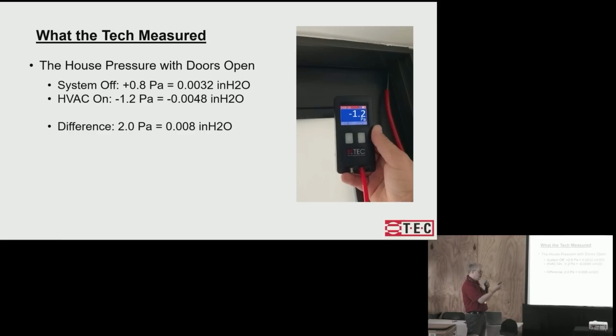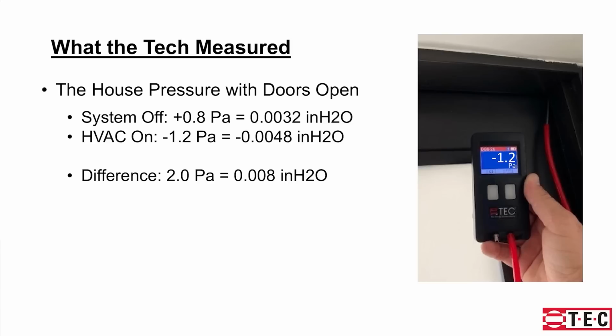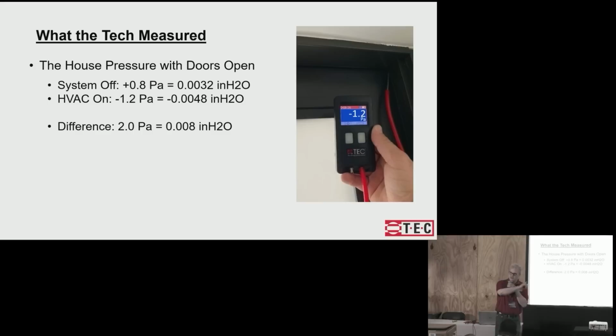It's important to recognize, when we start talking about wind, that on a really windy day you can't really do this test, because the wind might be fluctuating by 10 pascals. Are you going to see a difference of 2 pascals? Probably not. So you kind of have to wait for a calm day to do this test. So this is what's measured, and Jenry, how long did it take you to do this test?